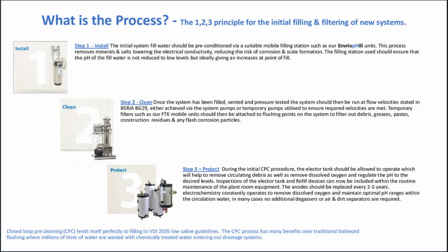So step 2 is clean. Once the system has been filled, vented and pressure tested, the system should then be run at flow velocities stated in BSRIA BG29, either achieved via the system pumps or temporary pumps utilised to ensure required velocities are met. Temporary filters such as our FTK mobile filters should then be attached to flushing points on the system to filter out debris, grease, paste, construction residues, and any flash corrosion particles.